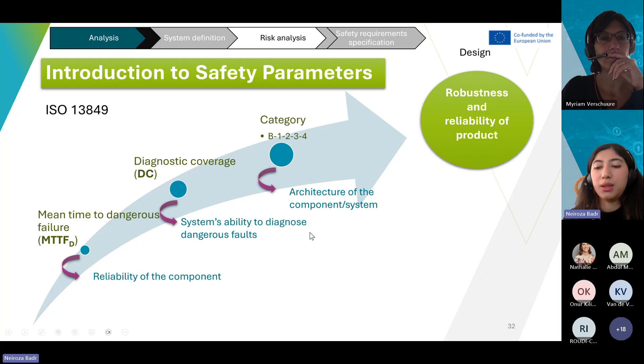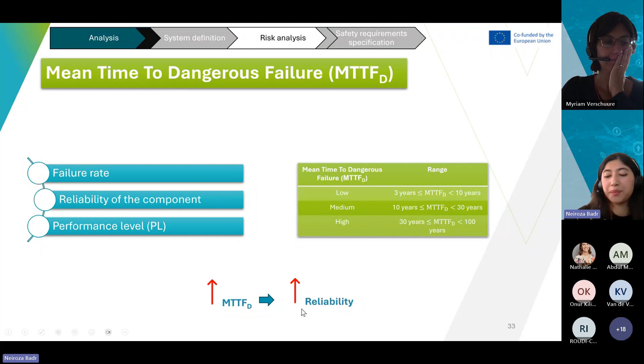So the first parameter is the mean time to dangerous failure, MTTFD. The mean time to dangerous failure represents the expected operational time before a dangerous failure occurs. So it is a measure of reliability and is used to estimate how often failures might occur. It is also a safety parameter that is used at the end to determine the performance level. It is expressed in years, in ranges from low to medium to high. So what you need to understand is that the higher the MTTFD of the component is, the greater the overall system's reliability is.